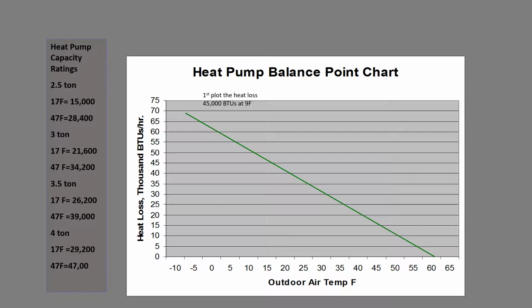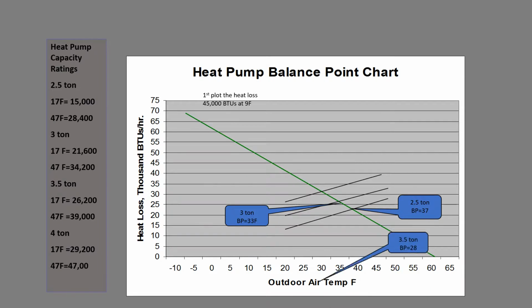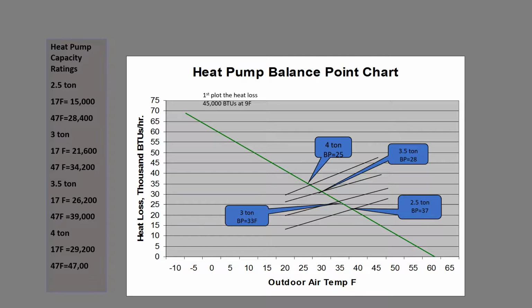So yeah, this house has a 45,000 BTUs at 9 degrees. Our first one here is a 2.5-ton, and if we just draw a straight line between the 17 and 47 degree AHRI rating points, you get a nice straight line. So the balance point where the two lines cross is 37. Not really a very good fit. The 3-ton gives you 33. We're getting closer. The 3.5-ton would give you 28. Nice fit. I think that'd be a very nice fit for this house.